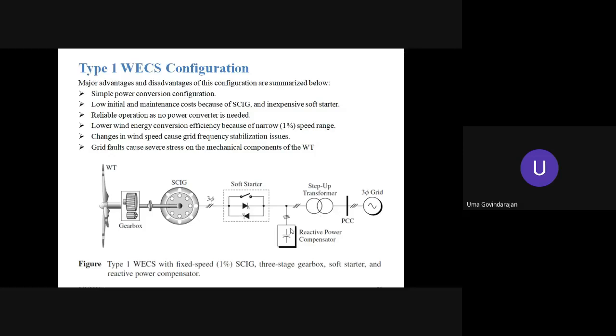Sometimes, as I mentioned earlier, the arrangement for reactive power support is also made separately, by using a bank of capacitors. It's a very simple and rugged power conversion configuration, with low initial and maintenance cost, an inexpensive soft starter, and reliable operation as no power converters are needed. But it has lower wind energy conversion efficiency because of the 1% speed range.